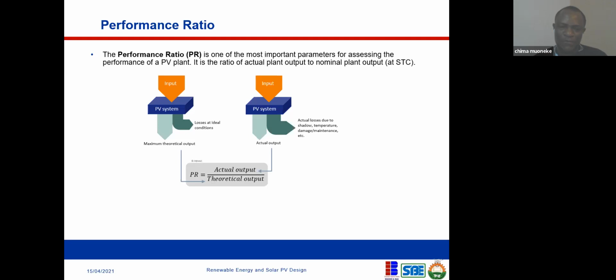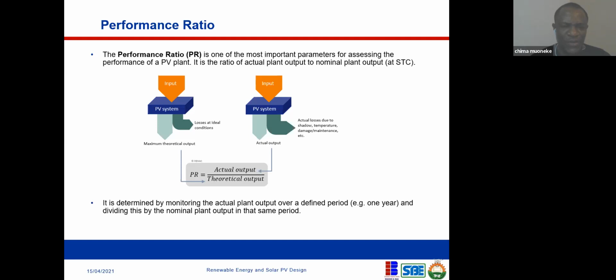So in actual sense, the formula for the performance ratio is the actual output, that is the actual energy that you get from that solar PV that is rated 300 watts peak, over the 300, that is the theoretical output. That solar module has been designed and labeled 300 watts peak, so it's supposed to give you 300 watts peak. So the actual energy that you get from that PV divided by that 300 watts is what gives you the performance ratio. When you do that, you're going to get something less than 100%. So that's what performance ratio is all about. It is determined by monitoring the actual plant output over a defined period, maybe 1 year, and dividing this by the nominal plant output in that same period.